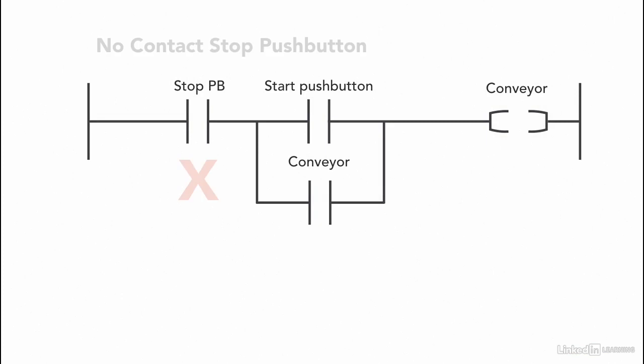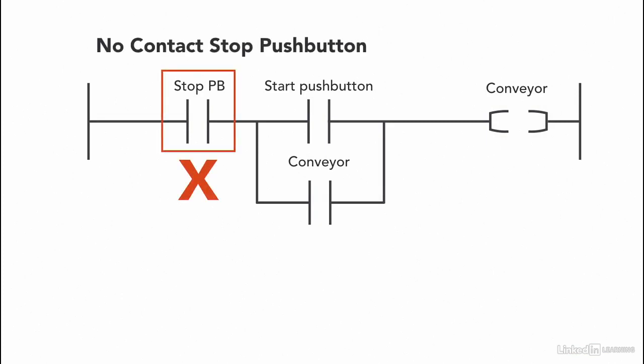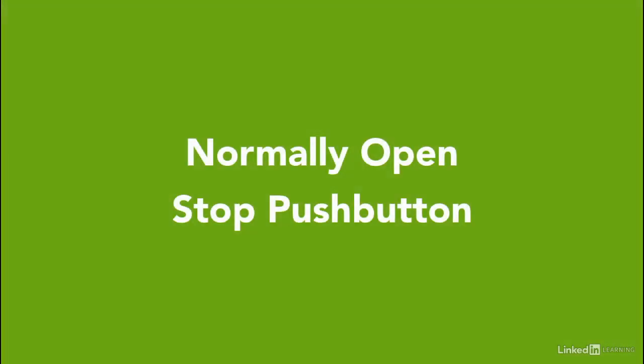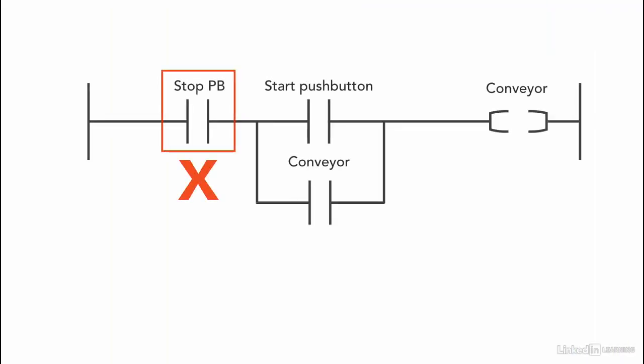Another mistake a PLC programmer might make is using an XIC instruction for the stop push button. Since we're using a normally open contact for the stop push button, we cannot use an XIC instruction, because then the stop push button would need to be pressed for the conveyor to start, and we don't want that.